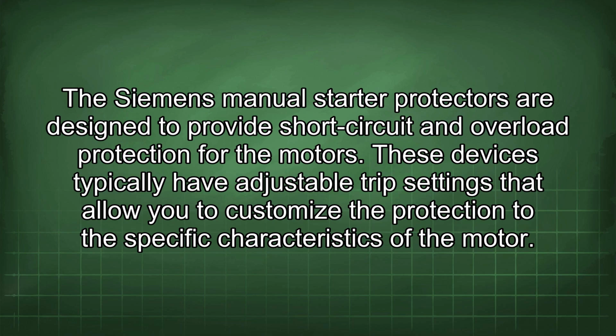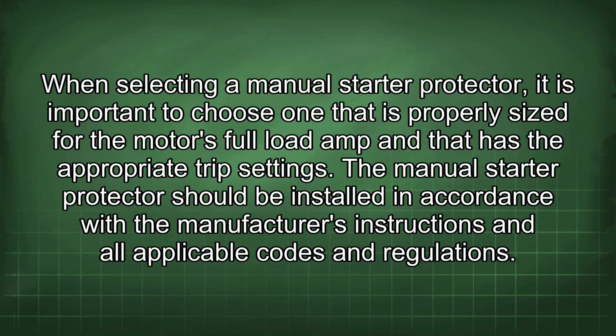The Siemens manual starter protectors are designed to provide short circuit and overload protection for the motors. These devices typically have adjustable trip settings that allow you to customize the protection to the specific characteristics of the motor. When selecting a manual starter protector, it is important to choose one that is properly sized for the motor's full load amp and that has the appropriate trip settings. The manual starter protector should be installed in accordance with the manufacturer's instructions and all applicable codes and regulations.